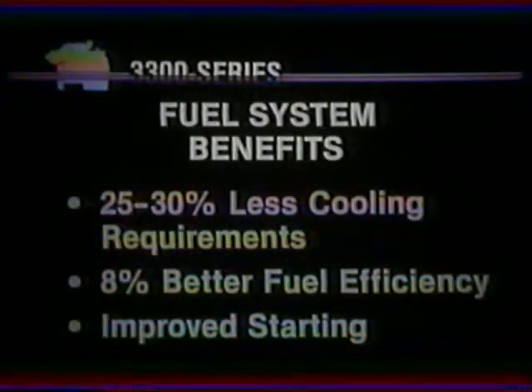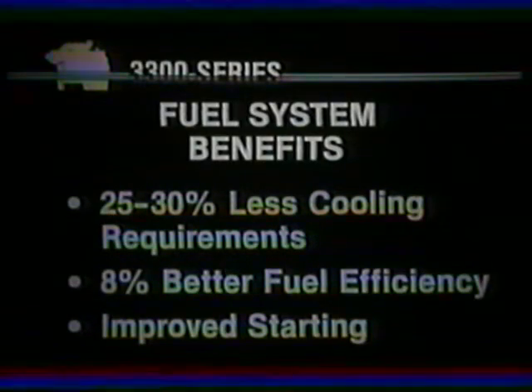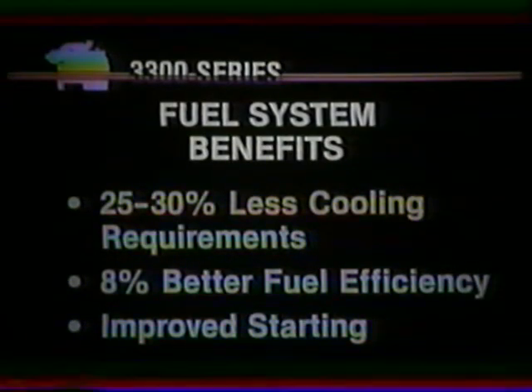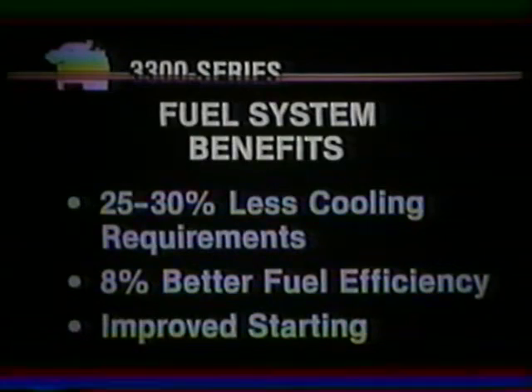3300 series engines with direct injection fuel systems offer the following benefits. Low jacket water heat rejection for reduced cooling system requirements, approximately 25 to 30% less. Improved combustion efficiency for improved fuel efficiency, approximately 8%. Excellent cold weather starting. All 3300 series diesel engines utilize the proven multiple pump fuel injection design. Combustion systems vary from direct injection to pre-chambered systems.